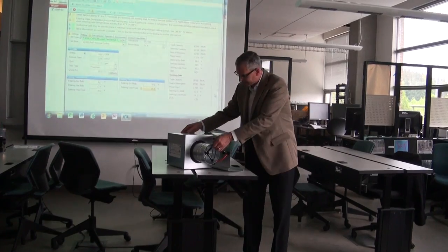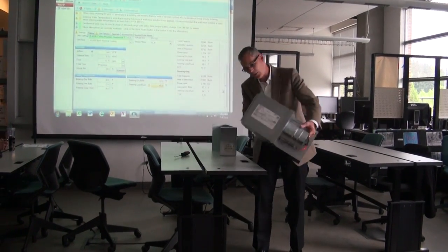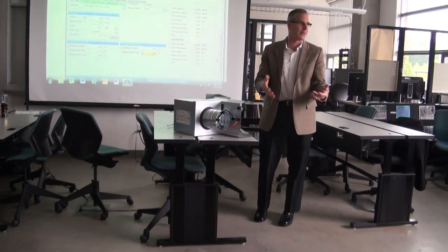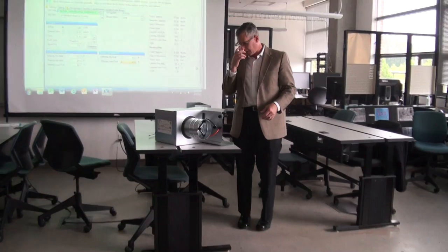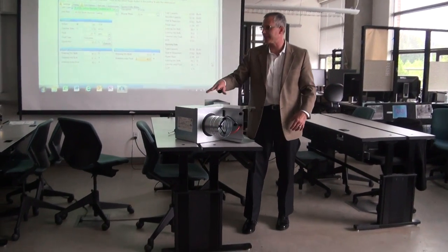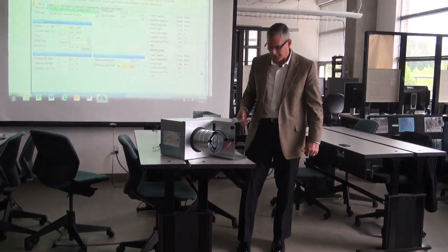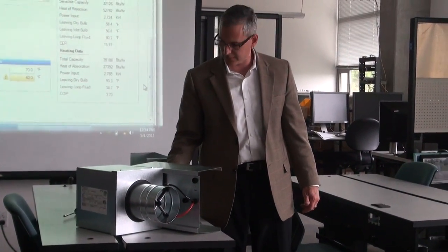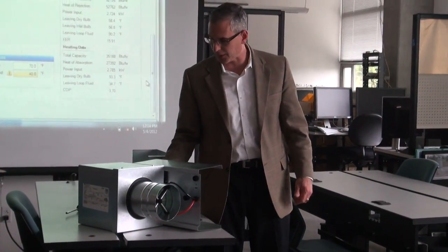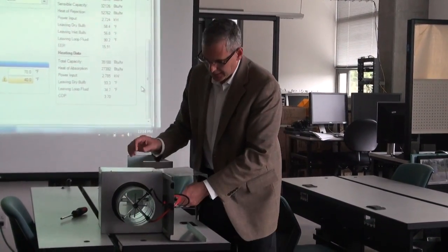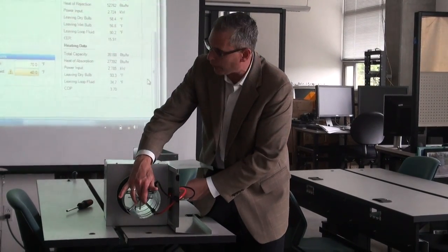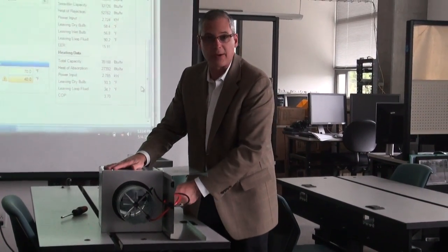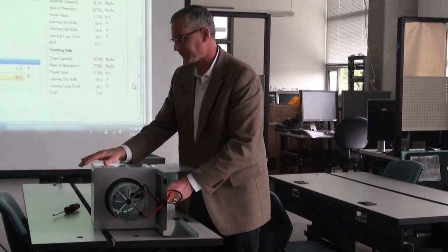This is what we call a single duct box or a squeeze box. They use the word single duct because in the past we did dual duct. It'd be two ducts, a hot and a cold side. Code doesn't allow that. Relate it to a fan power box, because they got fan power boxes all over. So this box is similar to a fan powered box in that it has an inlet flow sensor and it has a damper, a modulating air valve, they call it, or damper.